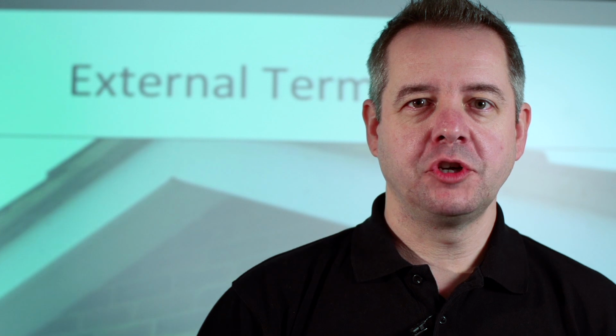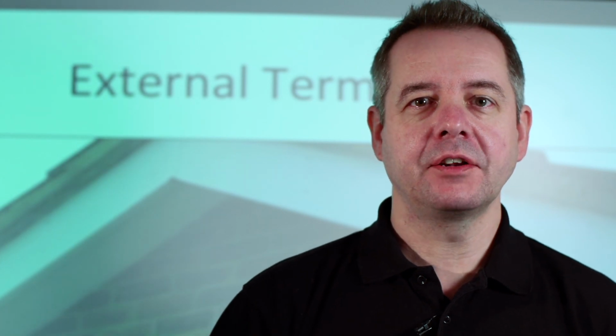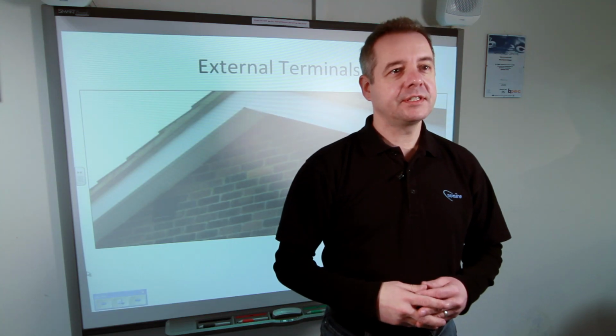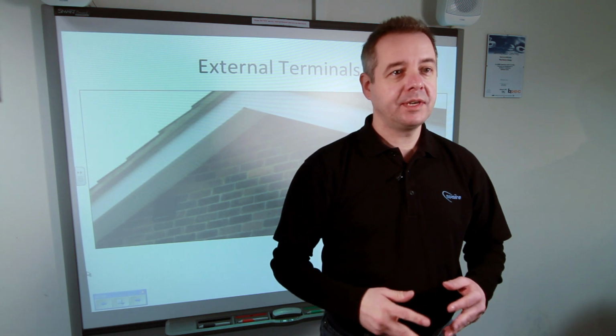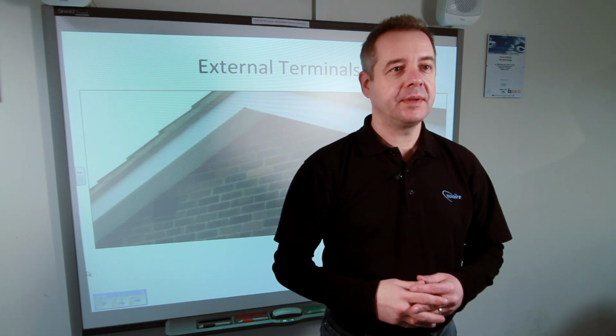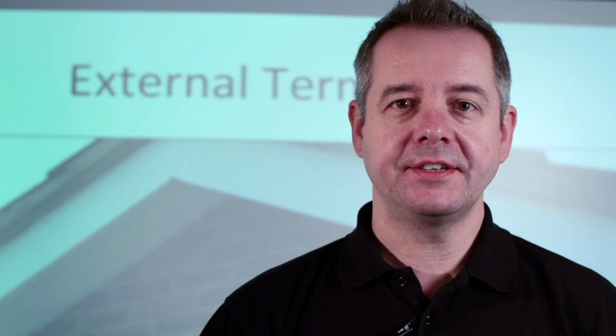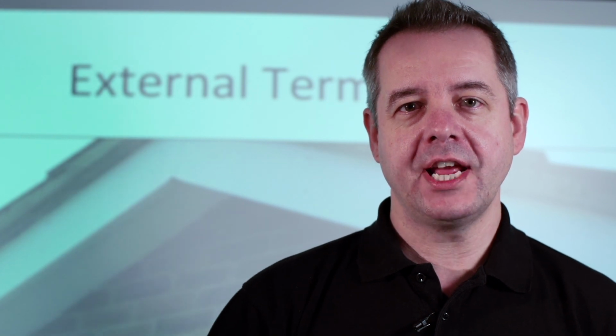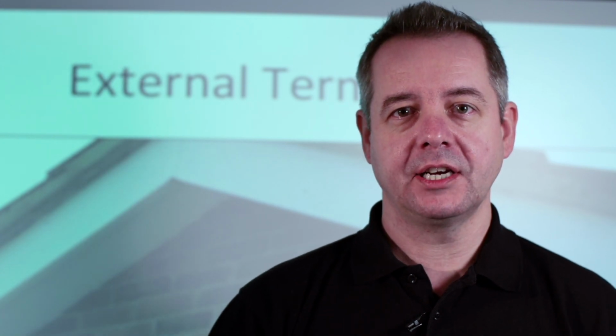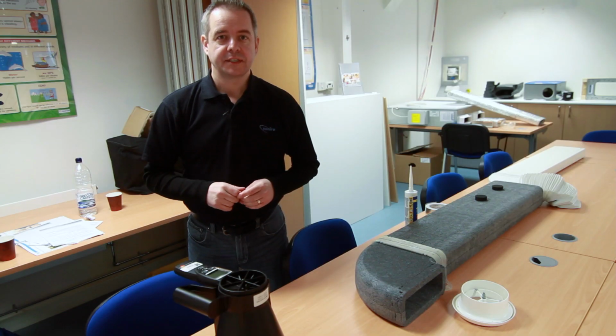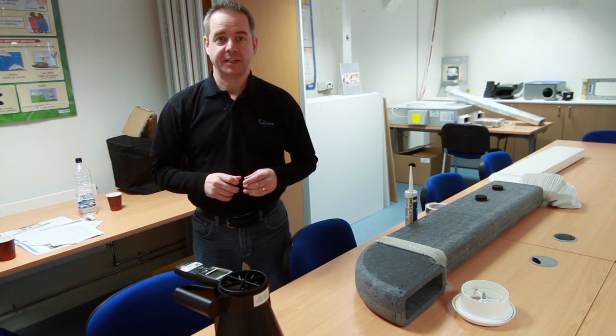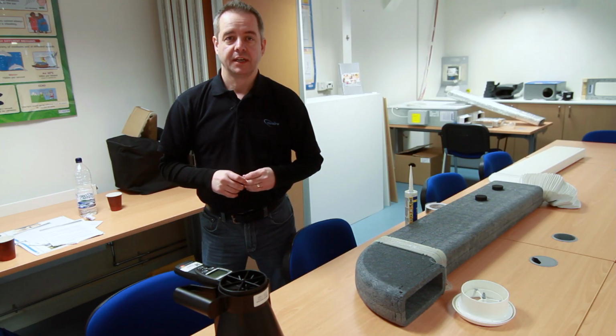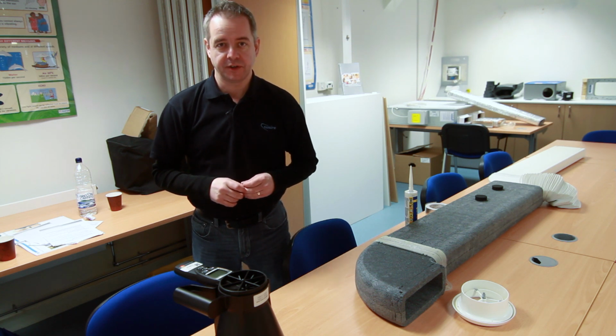Always use external terminations that are made specifically for mechanical ventilation. On a heat recovery system, it's very important that these external terminations are kept a minimum of 300 millimeters apart. This is to prevent the extract air from re-entering the building through the supply duct and causing condensation within the house. Once the system has been fully installed, it should then be commissioned to prove that the airflow rates achieve what's set out in Part F of the building regs.